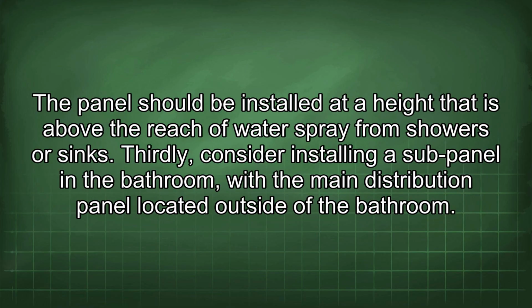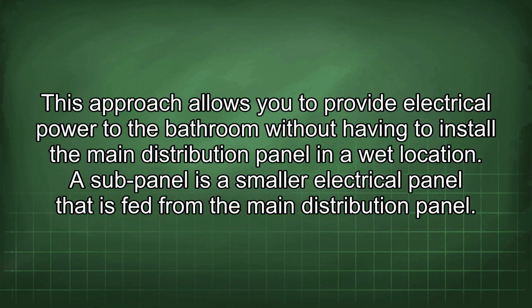The panel should be installed at a height that is above the reach of water spray from showers or sinks. Thirdly, consider installing a sub-panel in the bathroom, with the main distribution panel located outside of the bathroom. This approach allows you to provide electrical power to the bathroom without having to install the main distribution panel in a wet location. A sub-panel is a smaller electrical panel that is fed from the main distribution panel.